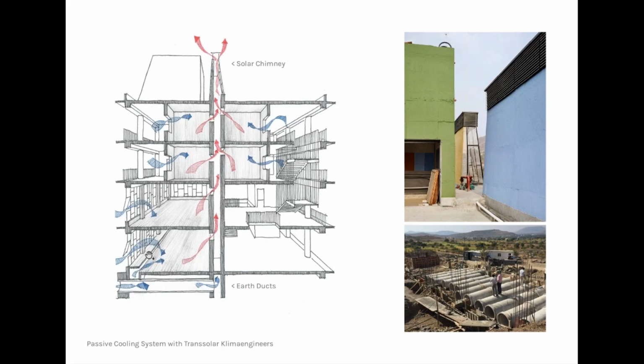Again, one of the things I learned very early on from Pratik is that temperature is one measure of comfort. The others are the amount of clothes that you have on, in terms of the kind of density and your ability to perspire and have that evaporation. The second is the relative humidity. The third is temperature, and the fourth is air movement. And so the success of the system, while it does achieve a kind of 5 to 9 degree temperature difference, is also based on the airflow and the air movement that is created by the convection, not just the temperature alone.